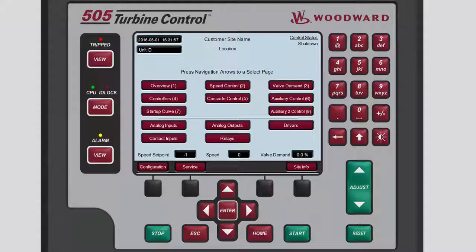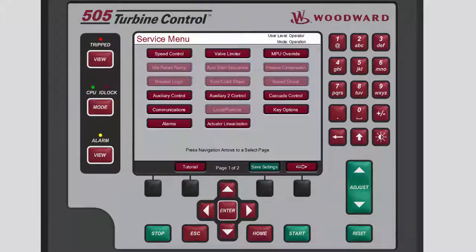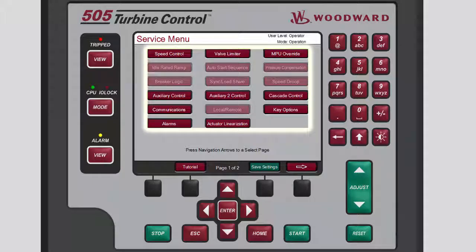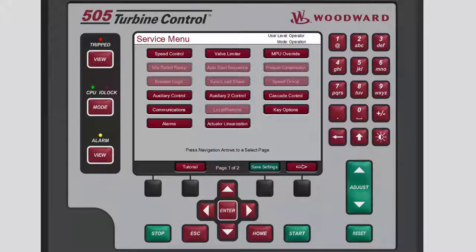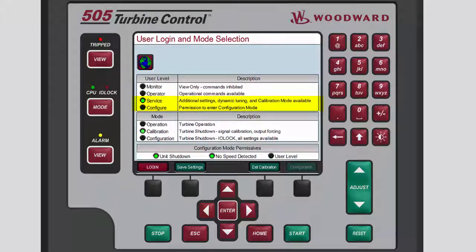To open the Service Menu from the Home screen, press the black Function key below Service. The Service Menu contains navigation buttons to all the service-related parameters and special features of the control. To select any of these buttons, use the navigation cross keys to highlight the applicable button, then press Enter. To make changes from the Service Menu, you must be logged in at either the Service or Configure User Level and the Unit must be placed in either Calibration or Configuration Mode.